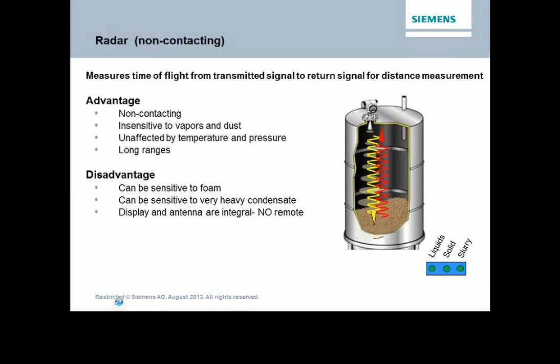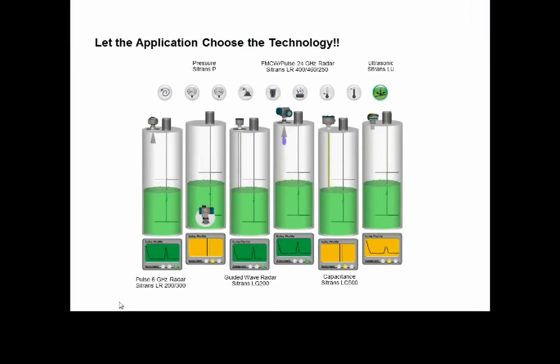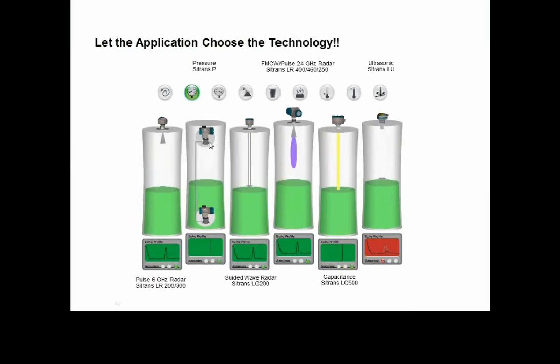So when you take a look at all the different applications that are out there and what our choices are when it comes to instrumentation, we can take a look at single pressure applications where we use a single transmitter. This would be for use in an open tank measurement, for example. When we have a vacuum on a tank, I can do the same thing with 2 transmitters, to be able to make adjustments for that.